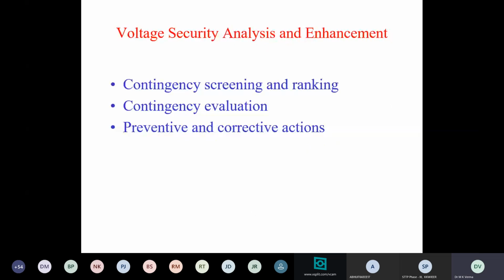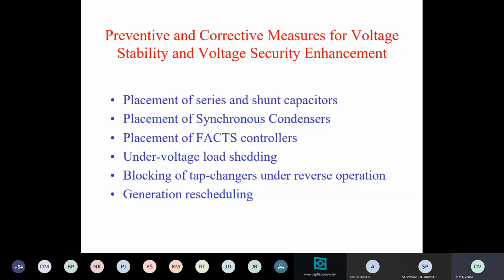Now, for voltage security analysis, you have to do contingency screening and ranking, contingency evaluation, and preventive and corrective actions analysis. These are different remedial measures against voltage instability. One is placement of series and shunt capacitors. Placement of synchronous condensers can control voltage. Placement of FACTS controllers like SVC, STATCOM, UPFC, etc. can control voltage.